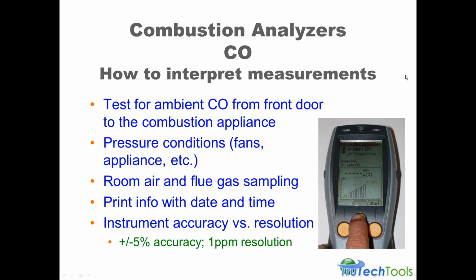So, just a little further information about ambient testing, we want to look at testing with pressure conditions that change, and we talked about a dynamic environment with the fans: ventilation fans, house fans, kitchen fans, bathroom fans that could affect the combustion air that's available. Do the room air and the flue gas monitoring together, room air to see if anything's leaking into the room, and the flue gas to see how much is being produced. It's very convenient to have the information printed up with the date, the time, the type of meter you're using, the serial number, etc. It gives you a very good record of your examination.